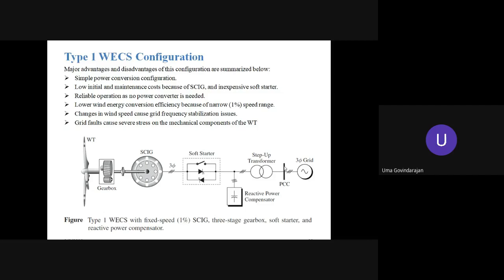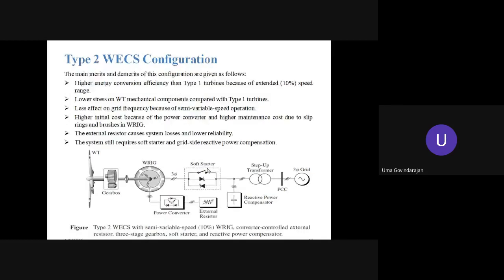So instead of the machine drawing the entire reactive power from the grid, a portion also can be supplied via this compensator, so that the dependence on the grid can be reduced. Without reactive power, generation is not possible for these machines. Therefore, this reactive power is support. Without this capacitor, the entire reactive power drawing will be from the grid only. To reduce the reactive power requirement from the grid, we can also employ shunt power devices. The total reactive power can be met partially from the grid and partially from the static devices.